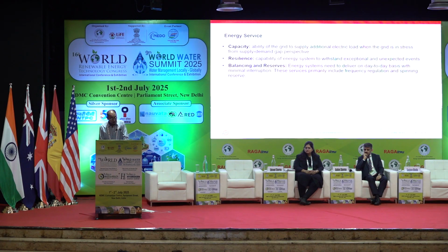A couple of other very important terms we talk about in energy storage are capacity and energy. Capacity is primarily the megawatt and energy is the megawatt hour. These are simple but very important terms, and they play a key role for the battery energy storage system at the utility scale, because this defines the backup duration the system can provide. This is one of the most important technical attributes based on application when someone is sizing and selecting the hybrid generation.